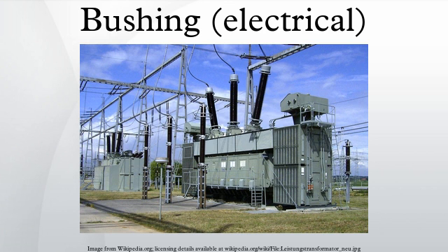The design of any electrical bushing must ensure that the electrical strength of the insulated material is able to withstand the penetrating electrical energy passing through the conductor, via any highly stressed areas. It must also be capable of enduring occasional and exceptional high voltage moments as well as the normal continual service withstand voltage, as it is the voltage that directs and controls the development of leakage paths and not current.